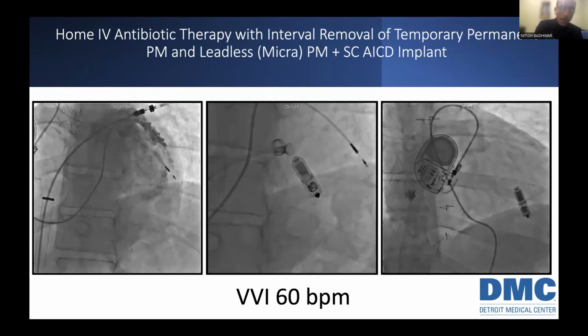Whenever you have a regular ICD and a different pacemaker, it doesn't matter whether it's a Micra or a sub-Q ICD, you have to pace the pacemaker at the highest output, induce VF, and make sure that the pacemaker output does not inhibit the VF detection on the ICD. Otherwise, the patient will go into VF, and if the pacing stimuli inhibit the ICD detection, the patient will not get a shock. That is what is required, whether you have a Micra, a sub-Q ICD, or a regular pacemaker, as long as they are two separate units, because the pacing stimulus can cause that artifact.